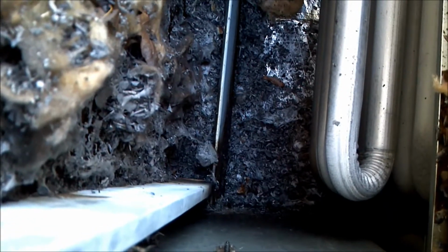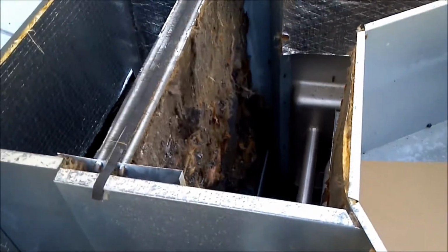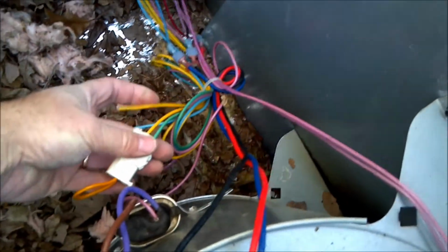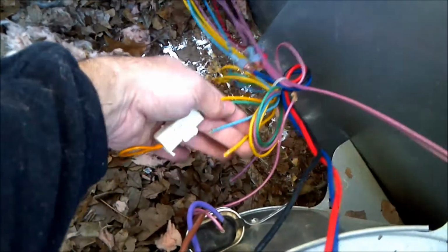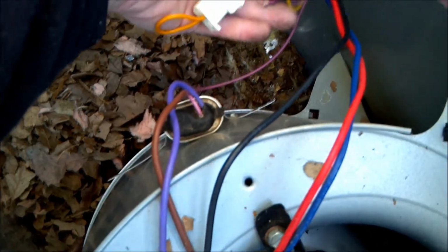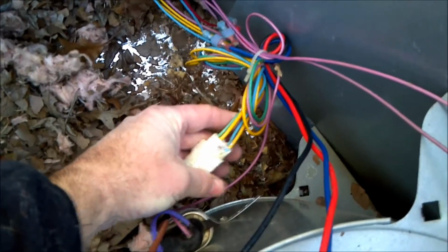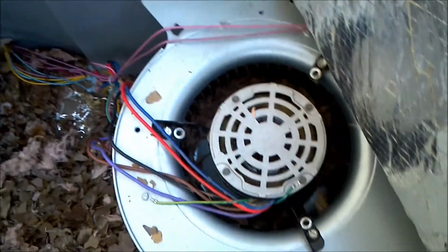And so I've got to go out here. I've got to clean all that evaporator coil off and clean all the soot. And then down here, the squirrel even chews through the wiring harness here, and you can see several of the wires were clean cut through there. He just chewed right through those wires there. I've got to check out the fan and the capacitor, make sure this is all working still, and clean out this compartment below at the bottom. The insulation on the bottom is all chewed up as well.